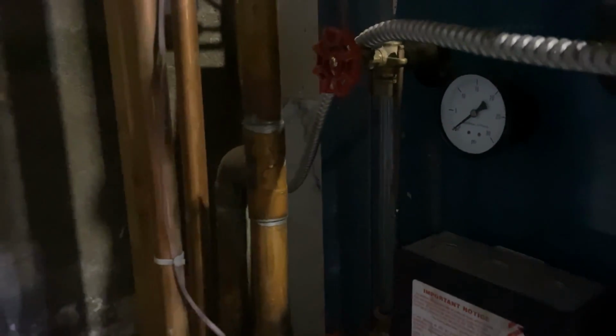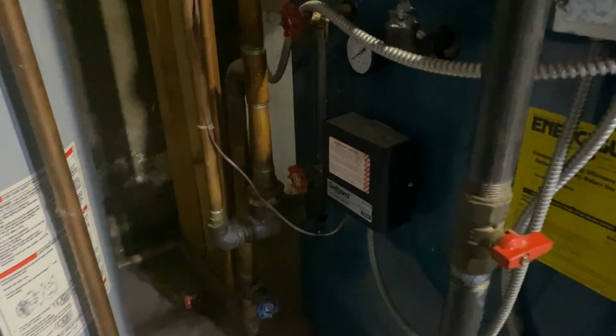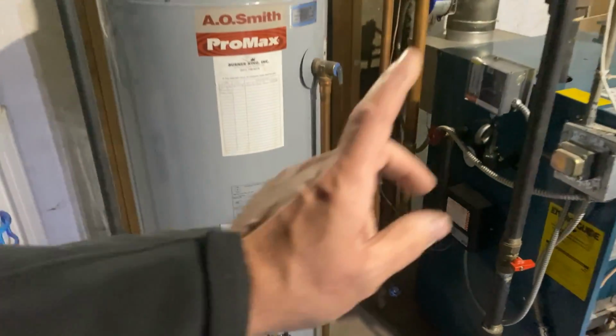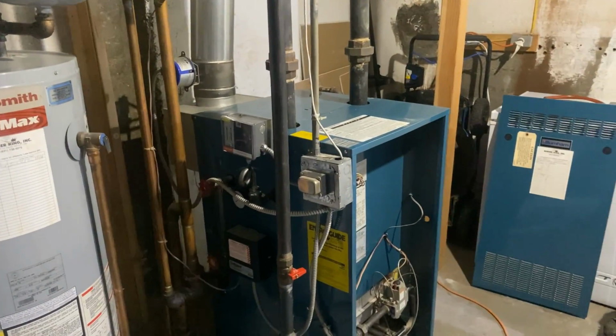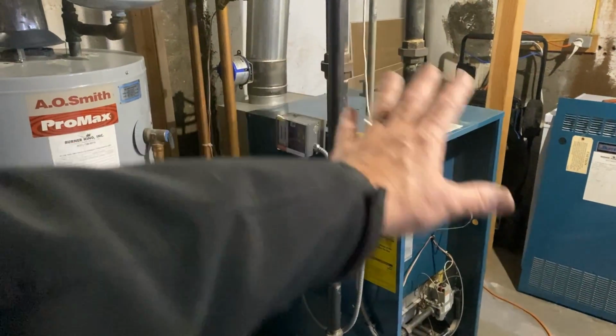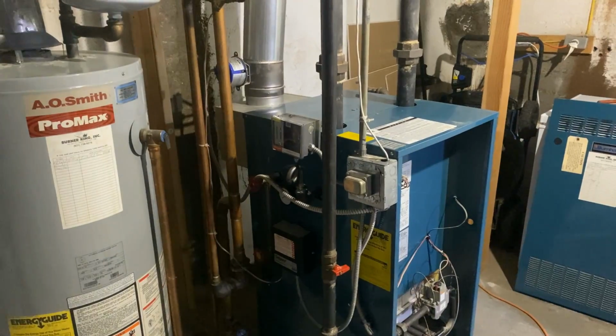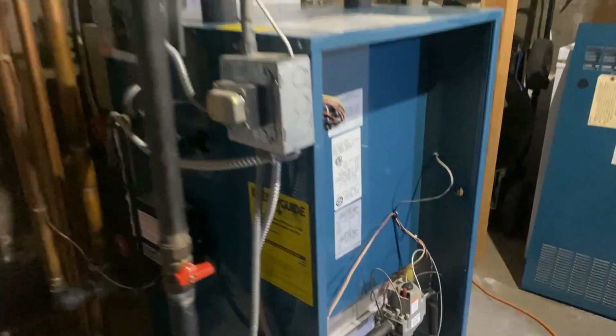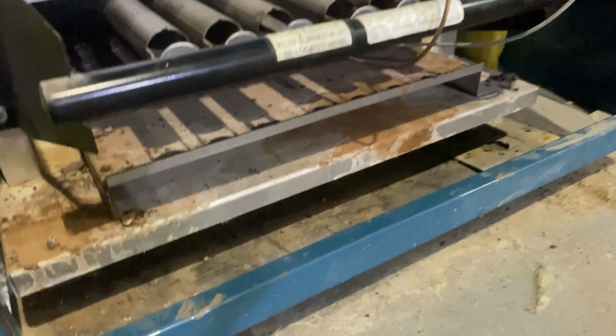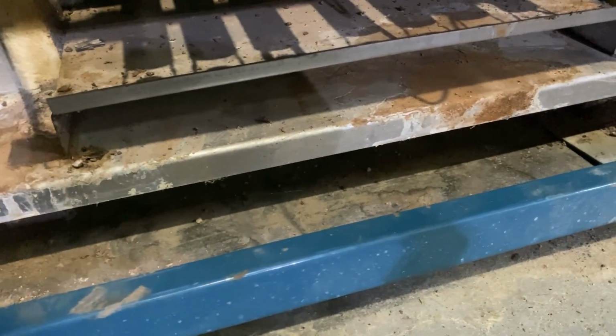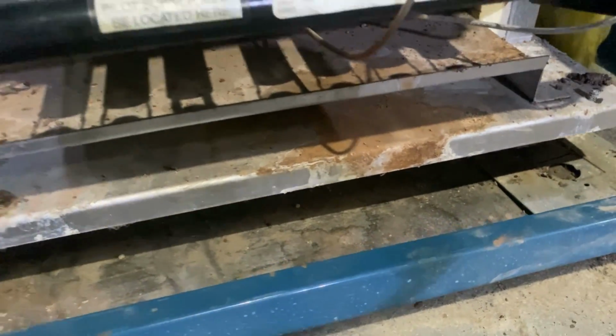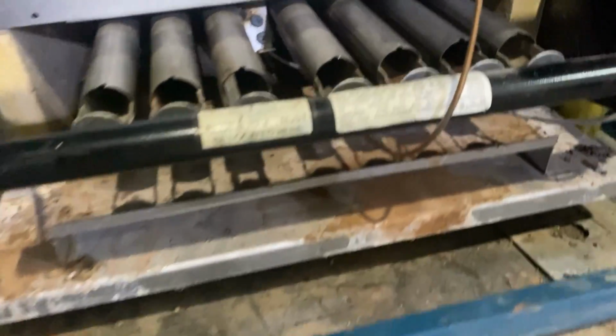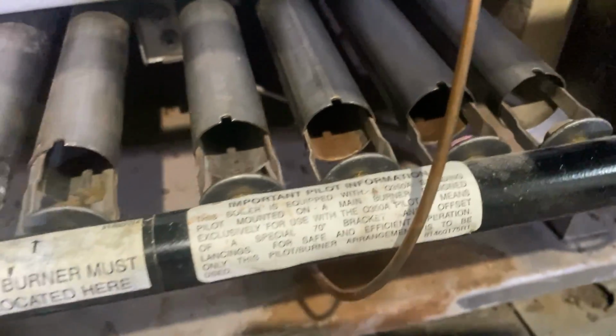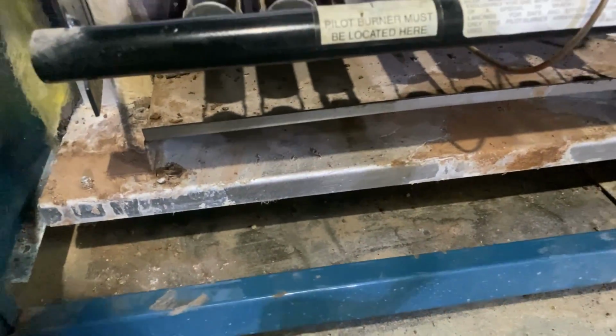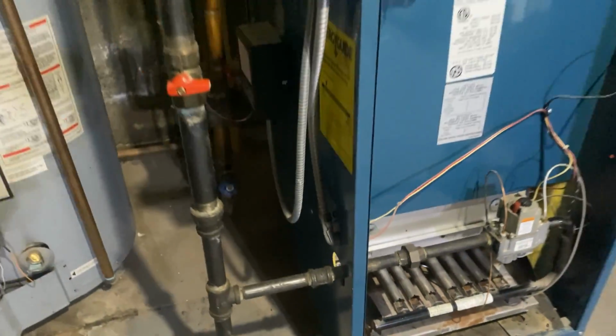Now we are replacing this boiler because there's a hole above the water line on the cast iron block, in the steam chest area. It's also evident by the rustiness that you see down there. It's water dripping down. You've got a steam boiler and you've got rust in your burner tubes or in the bottom of the combustion chamber, you're going to need a new steam boiler.